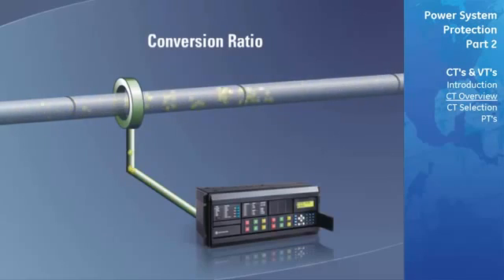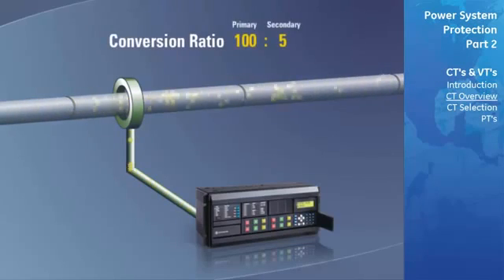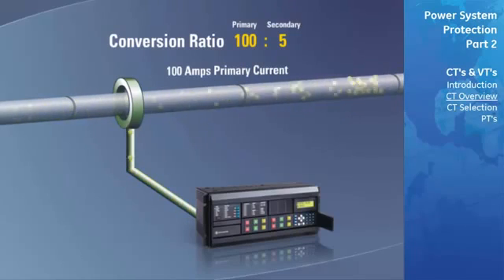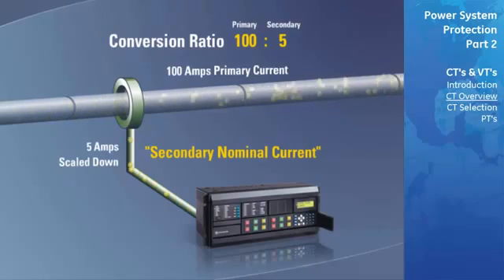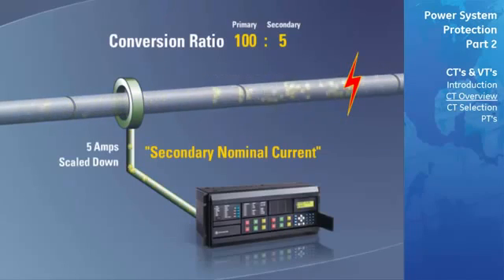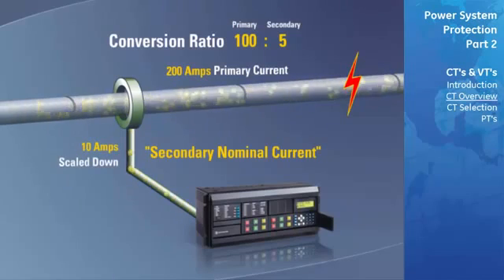In this example, our conversion ratio is 100 to 5, meaning that if 100 amps are passed through the primary phase wire, the CT will scale this down to 5 amps and direct it to the relay via the secondary windings. The 5-amp measure is known as the secondary nominal current. If a fault were to occur on this phase that increases the primary current to 200 amps, then 10 amps would be passed to the relay through the secondary windings consistent with the ratio.